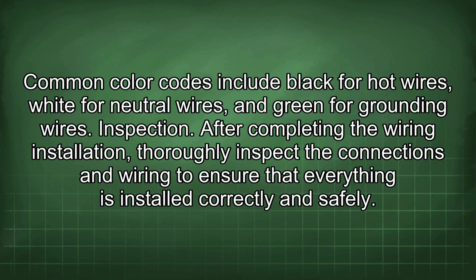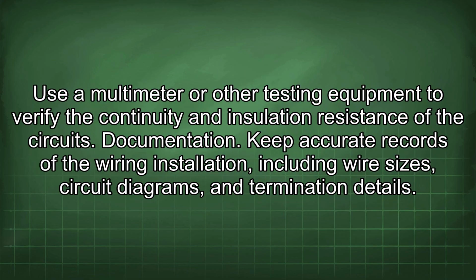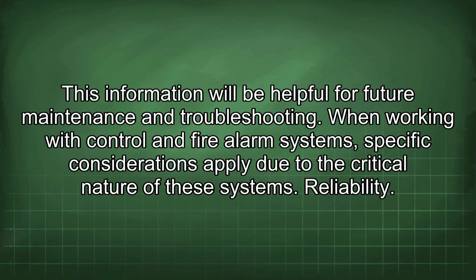Inspection. After completing the wiring installation, thoroughly inspect the connections and wiring to ensure that everything is installed correctly and safely. Use a multimeter or other testing equipment to verify the continuity and insulation resistance of the circuits. Documentation. Keep accurate records of the wiring installation, including wire sizes, circuit diagrams, and termination details. This information will be helpful for future maintenance and troubleshooting.